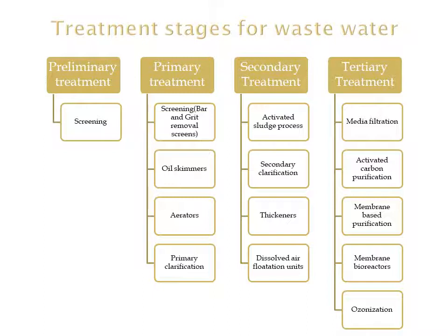And tertiary treatment is the final filtration treatment, and here media filtration can be carried out, in which a media bed is used that is made up of charcoal, sand, gravel and so on. When water is ultimately filtered through that bed, it becomes pure. Activated carbon purification is also used. Here activated carbon adsorbs the various impurities, if present in the water after the treatment, onto its surface. Mainly it adsorbs the organic compounds which are present in the water.